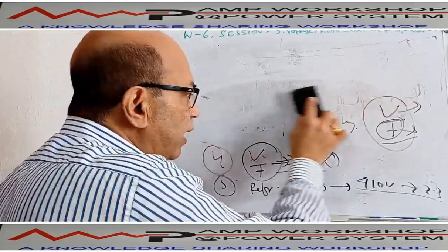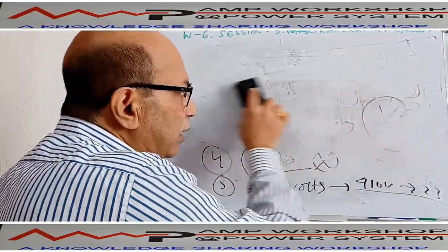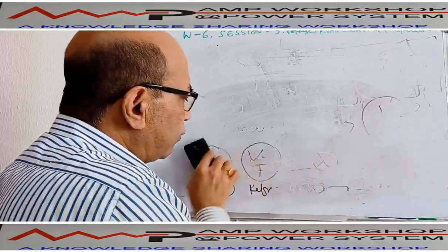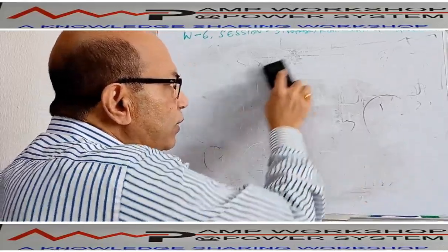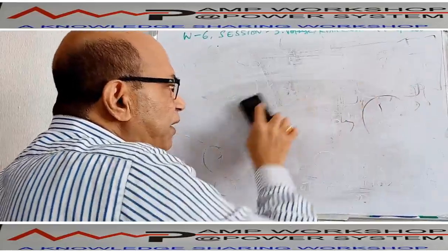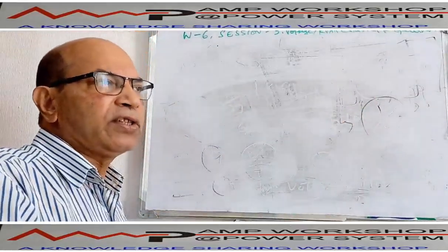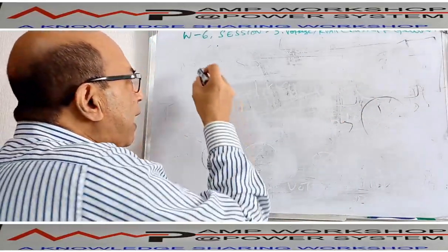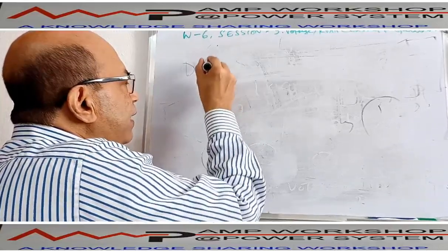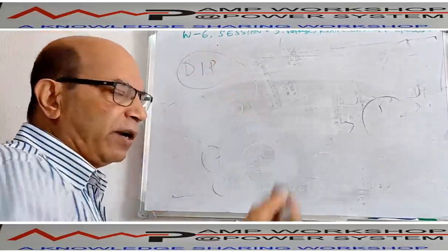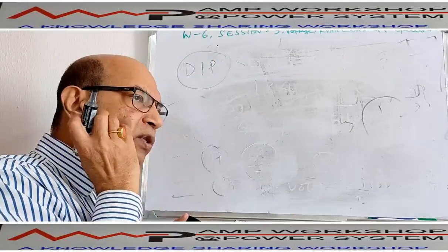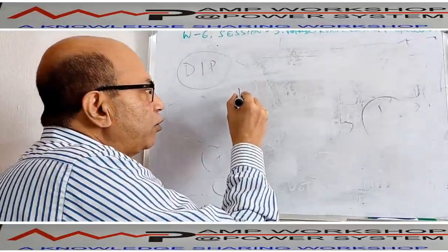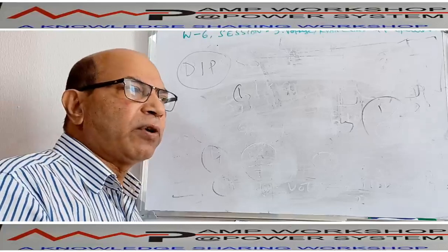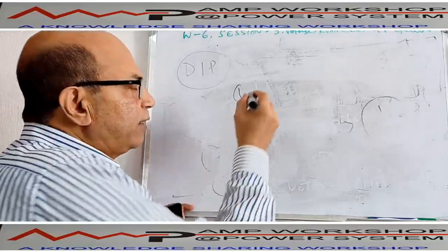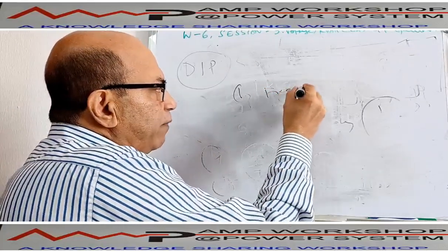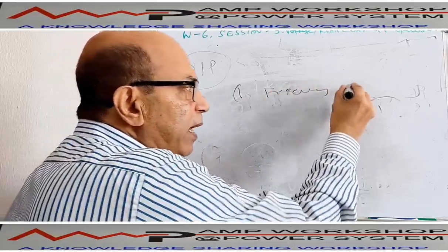You know DIP, we know that dual in package, dual in package. That is called a DIP, dual in package switch. That is generally used on all PCBs. This dual in package switch is the DIP switch. There are multiple DIP switches available in various AVRs of different makes. So mainly, what are the switches available? One of the switches is, you know, this AVR can be used for 50 hertz or 60 hertz. So there is a frequency setting. At what frequency do you want to use this AVR? It is 50 hertz or 60.